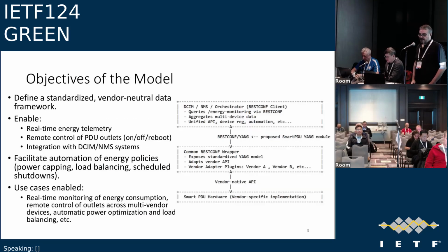So the objectives of the model is to define this standardized and vendor-neutral approach for controlling the smart PDUs, retrieving information and controlling, so that we can have real-time energy telemetry and have control on top of these PDUs at outlet level or the entire PDU itself. So facilitating the operation at the end, automation and operation. Use cases that we think could be enabled, apart from the monitoring, would be the remote control of the outlets, automatic power optimization, load balancing, and so on.